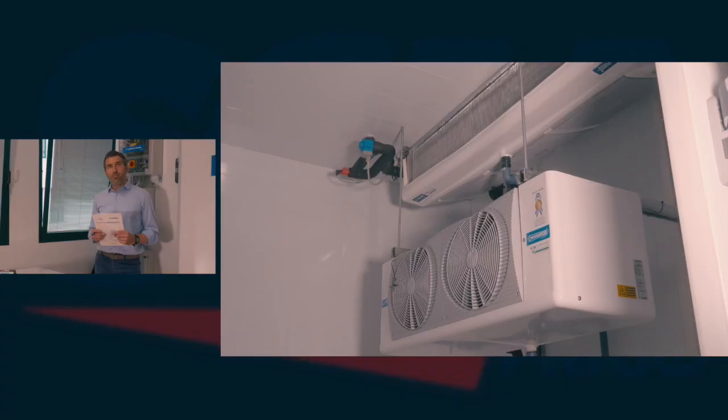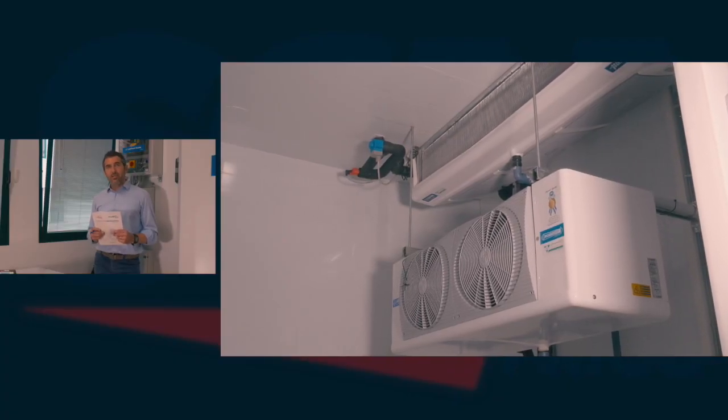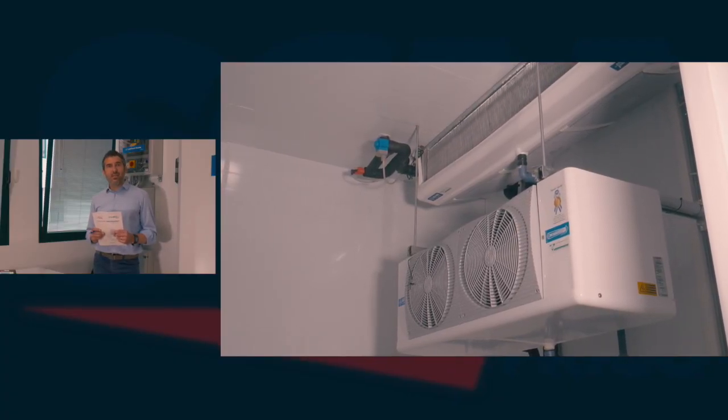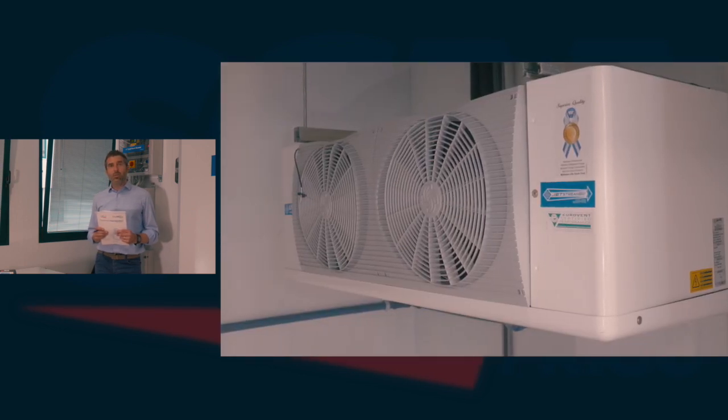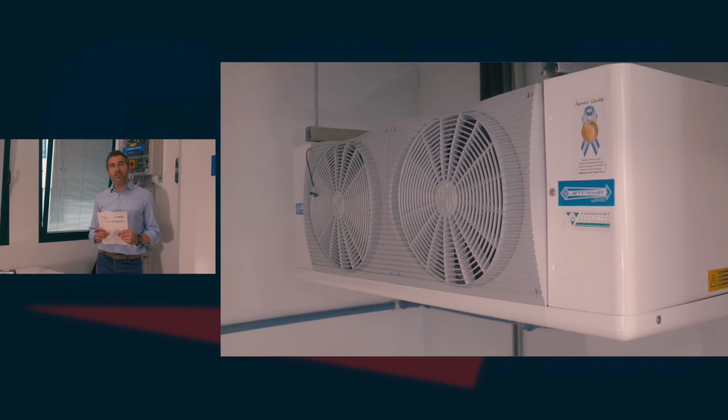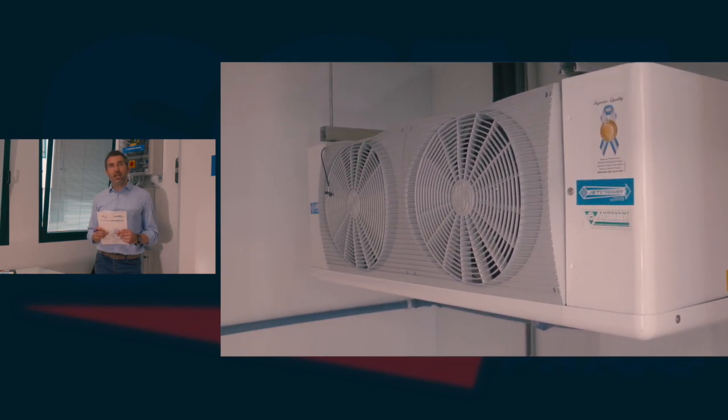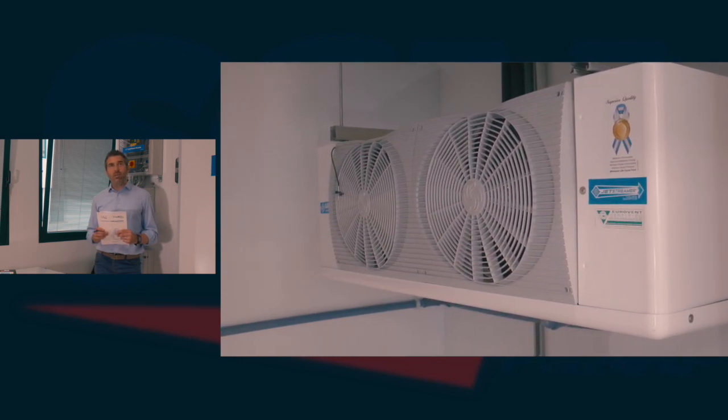This unit is connected to a single evaporator located inside the low temperature cold room. The evaporator control in this case is an MPX Pro unit, and the expansion valve is an E2V-C stepper valve.